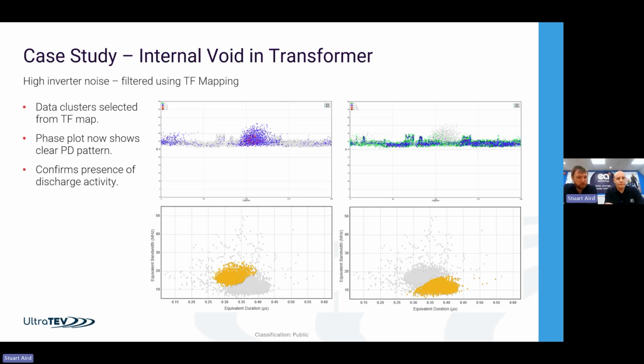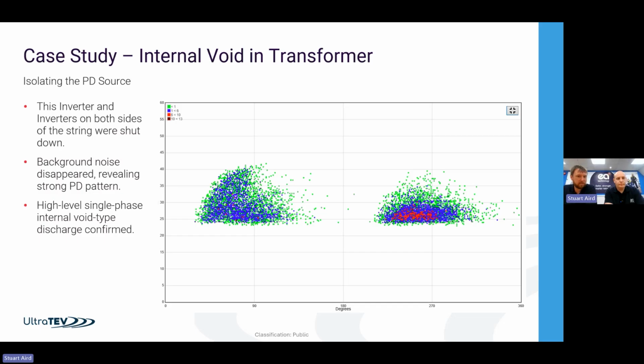So you can see the two half clusters there. This is the same measurement, but with inverters on both sides of the string, and also locally, turned off, and we can see the background noise now goes, and we've just got the pure PD signal. So it's a raw data capture, but with that background noise removed.